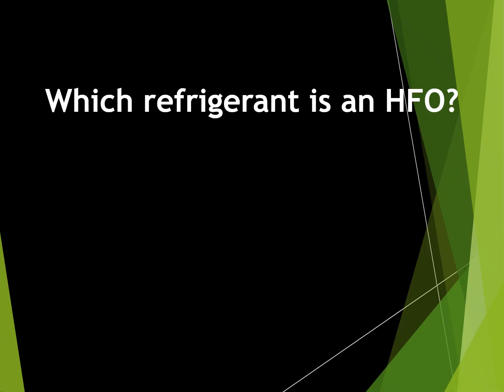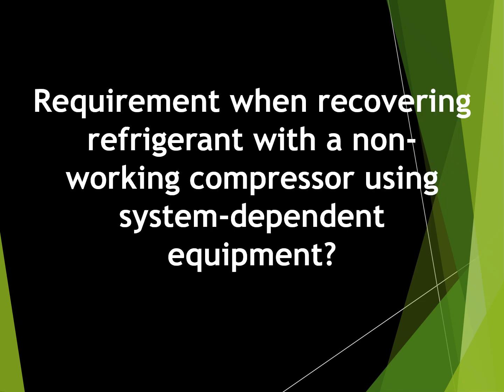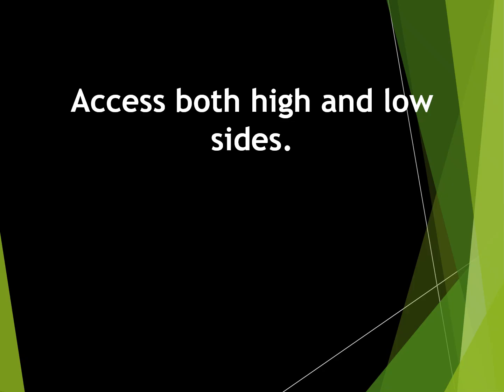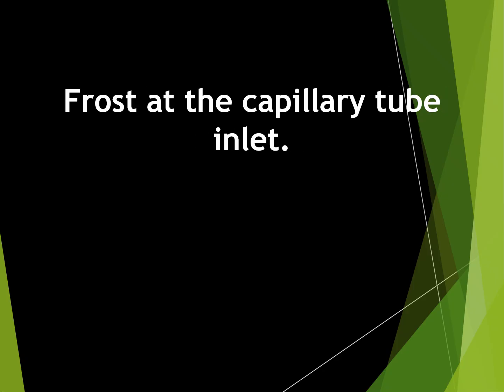Which refrigerant is an HFO? R1234YF. Requirement when recovering refrigerant with a non-working compressor using system-dependent equipment. Access both high and low sides. Sign of moisture in a sealed system. Frost at the capillary tube inlet.